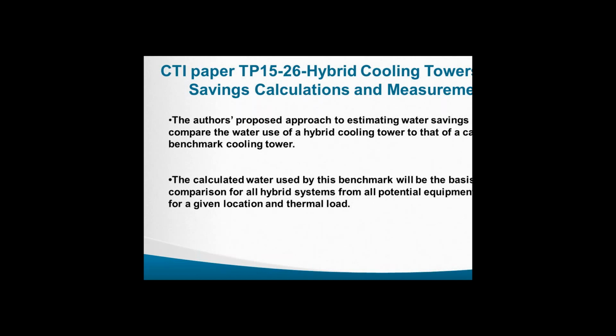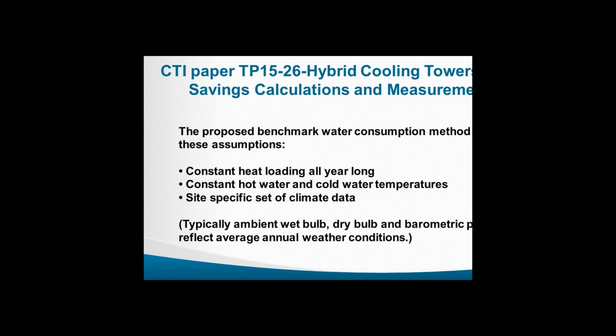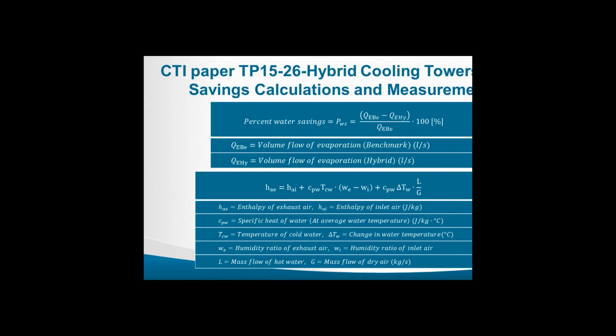So, a benchmark cooling tower, same design conditions, compared to the hybrid cooling tower under the same design conditions, showing what the water savings are between the two. Constant heat load, constant hot and cold water temperature set your guideline, your benchmark. I'm not going to go through all these equations, but they involve enthalpy and humidity ratios.